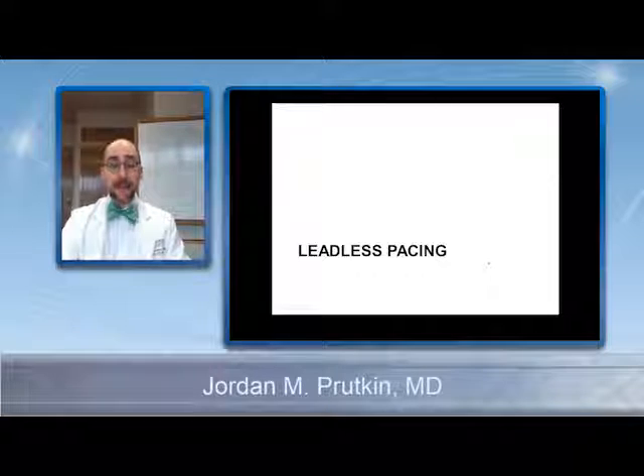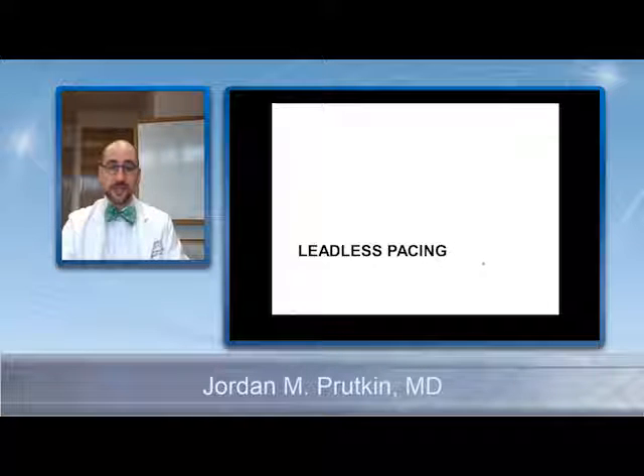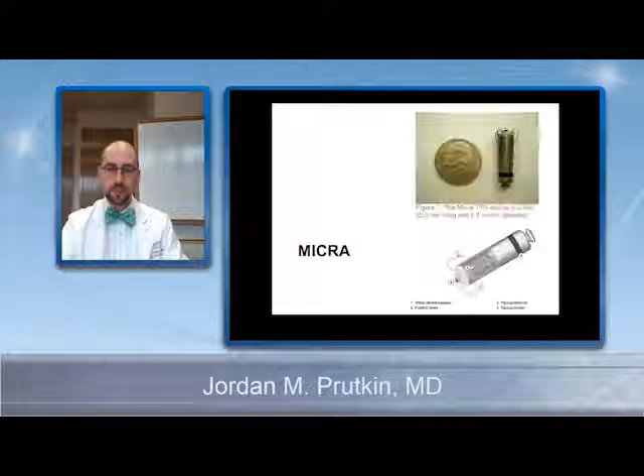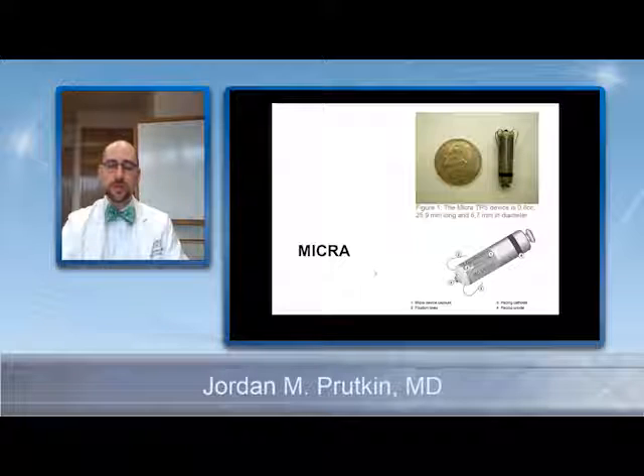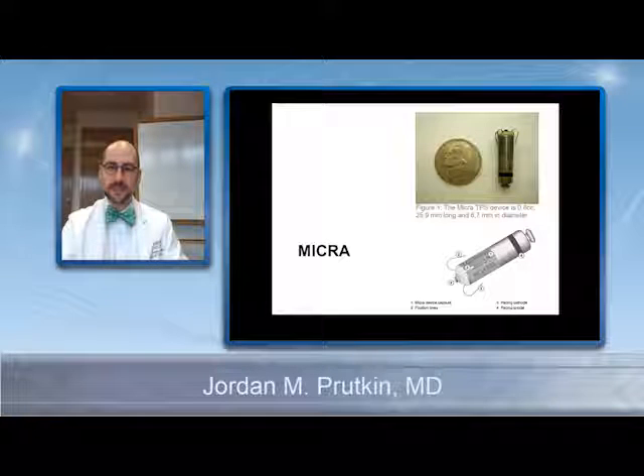All right, one of the last or other new technologies that I'm going to talk about is leadless pacing. So this, in my mind, really is the future of pacemaking and pacemakers. There's currently one FDA-approved leadless pacemaker available, and this is the Micra device. And you can see the device here relative to the size of a nickel. This is the entire pacemaker. This has the battery, this has the circuitry, this has the electrode at the tip, and it has these tines to keep it in place.